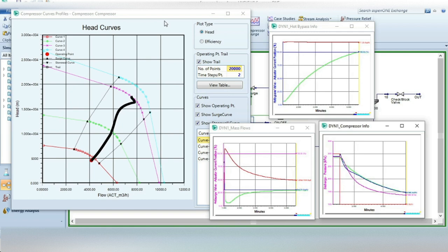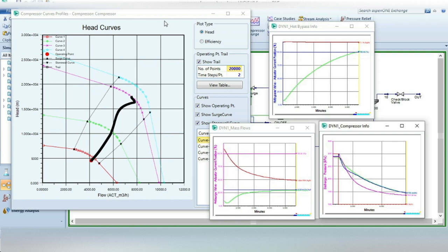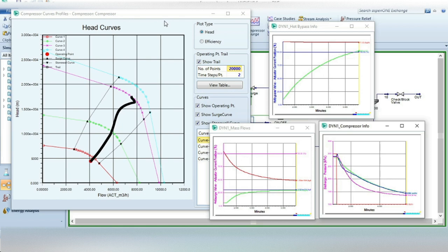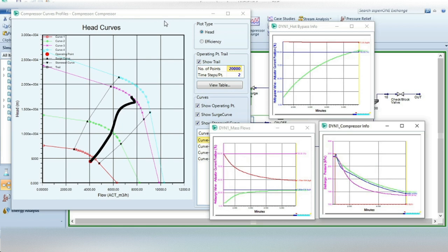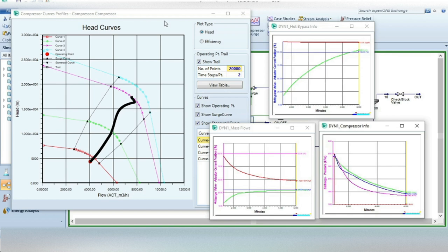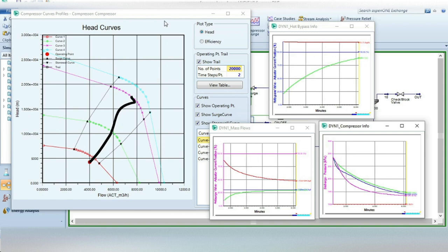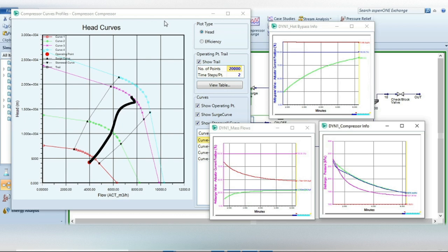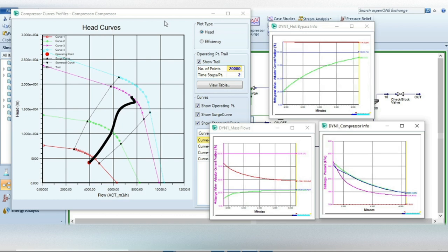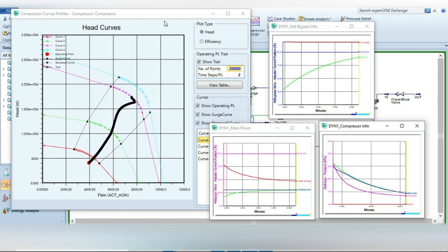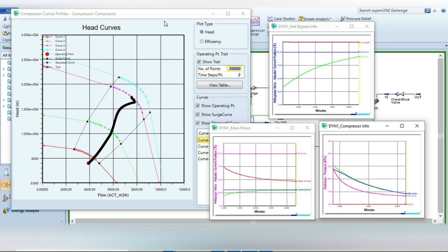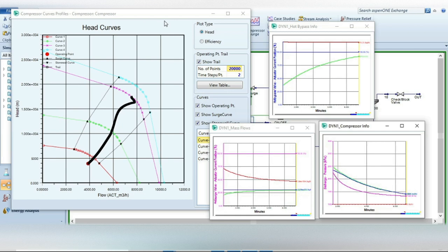Well, now you can see that the compressor performed within the boundary limits of the surge line and the stonewall line. So this is how you can tune different parameters, particularly the opening positions of the anti-surge valve and hot bypass valve, according to different emergency scenarios that happen during operation. This is a very useful tool for process and operation engineers. Similarly, you can now perform the analysis for the other scenario, the control shutdown. I already checked that with the same value, 0.1, for the CV of the hot bypass valve, it was doing really great.